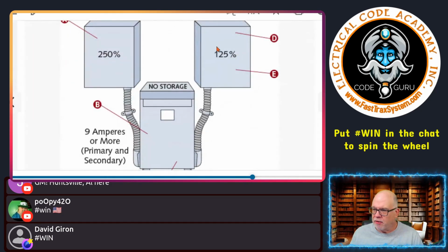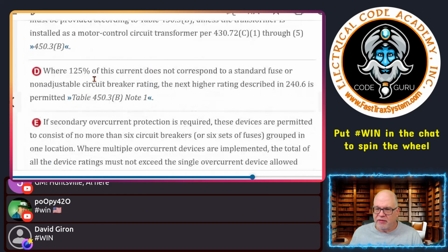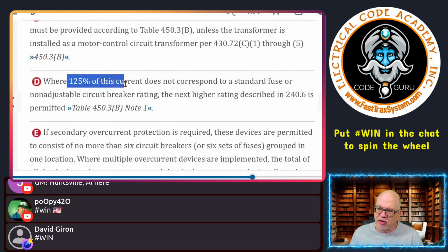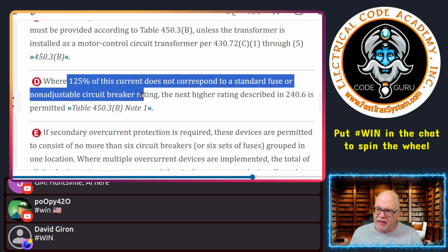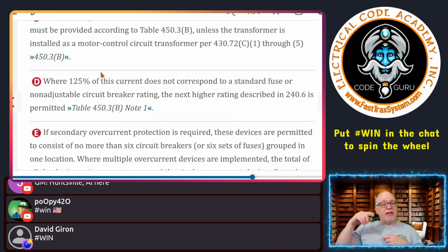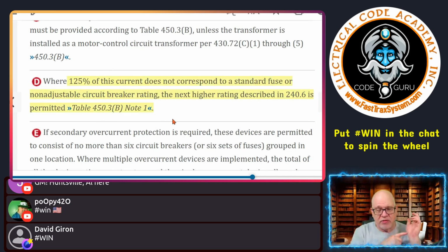D, this is the secondary. It says where 125% of the current does not correspond to a standard rated fuse or a non-adjustable circuit breaker rating, and again, we get the note that comes back so that we can use the next size up rule. So this is the example where the 250% on the primary is a maximum. It can be less. It doesn't have to be 250. That's why I told you most engineers will do it at 125% so that the conductors as well as the protection are aligned together. It's usually what happens.